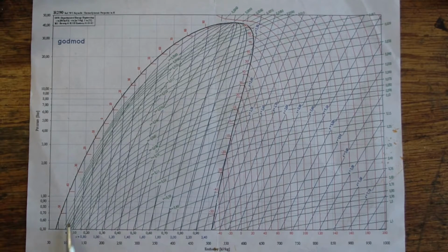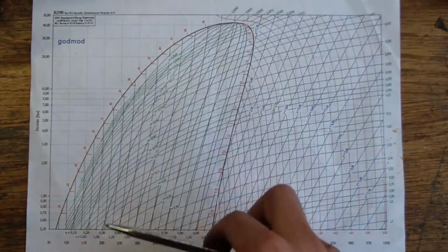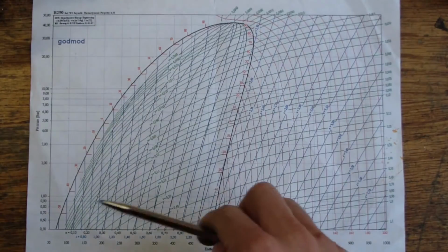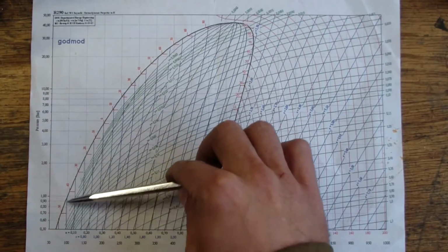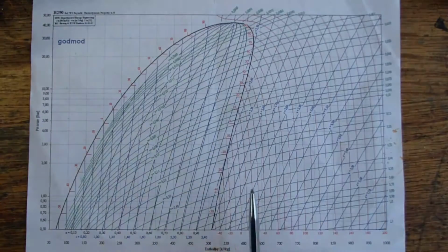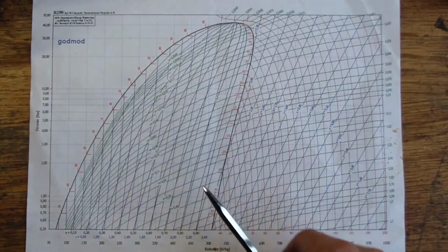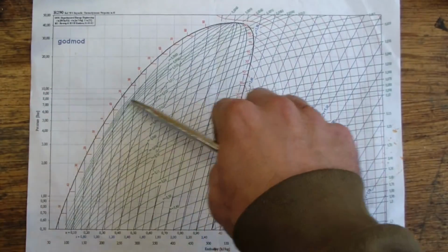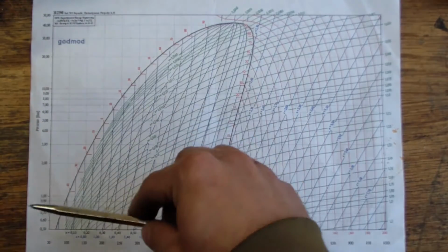If we travel from left to right, we're increasing in the heat content of the refrigerant. If we go from the bottom to the top, we're increasing in pressure. This is logarithmic, largely, I think, because it fits on the page a lot better, it's easier to work with, and it more or less linearizes the temperatures. If we go upward on this side, we see higher temperatures, and mostly left to right on this side, we see higher temperatures. In the middle of the horn, temperatures are horizontal, as this is the saturation curve. So anywhere within this curve, the refrigerant exists in both a vapor and a liquid state.